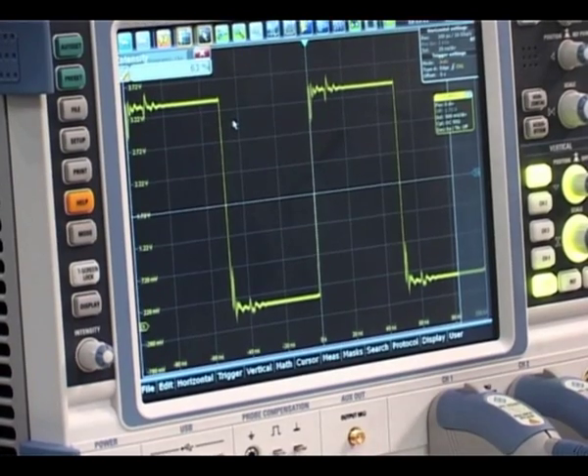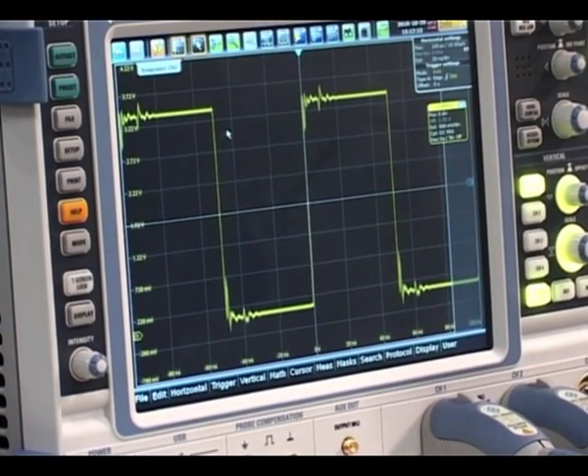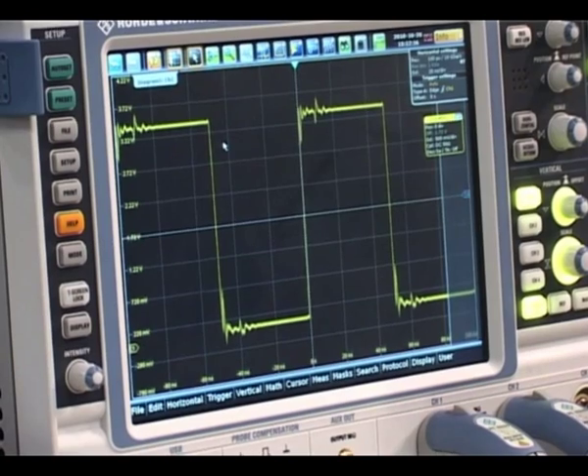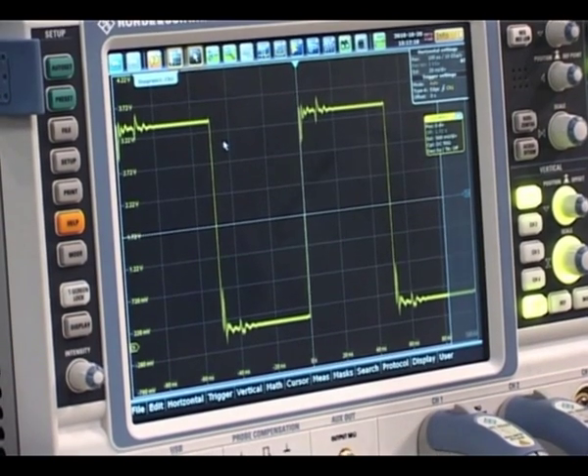The reason we can see this flicker is the very fast update rate of these scopes. These scopes can sample data and display up to a million times per second which is unprecedented, particularly if you're looking for rare faults, glitches, or transients on a signal.